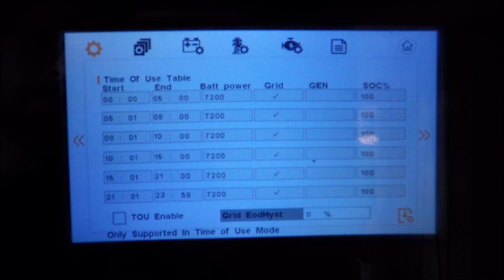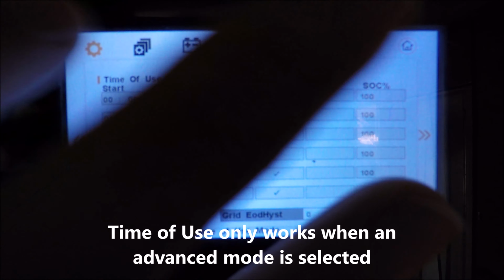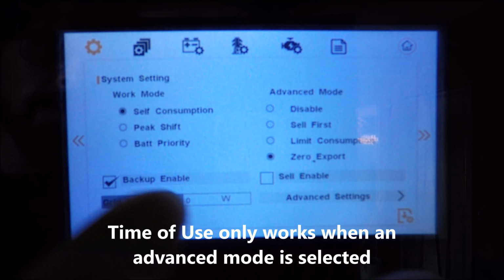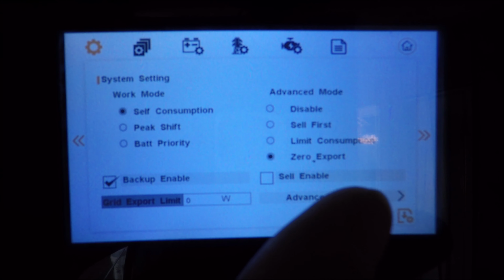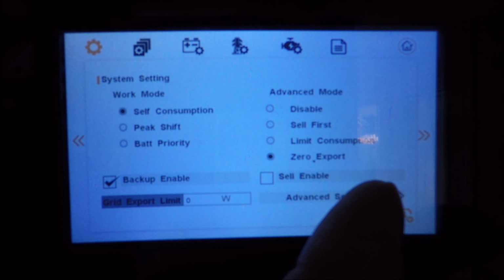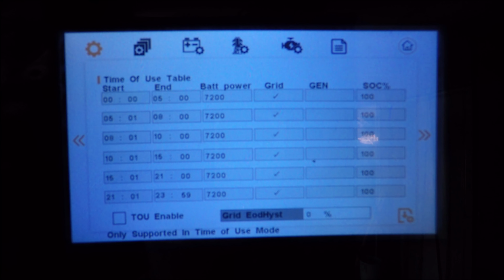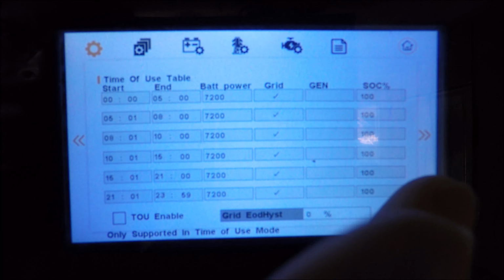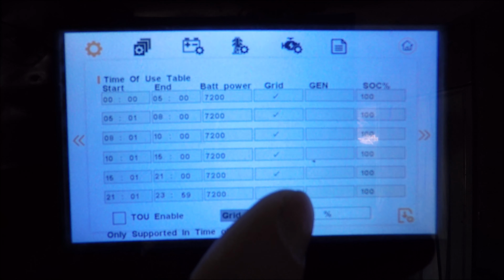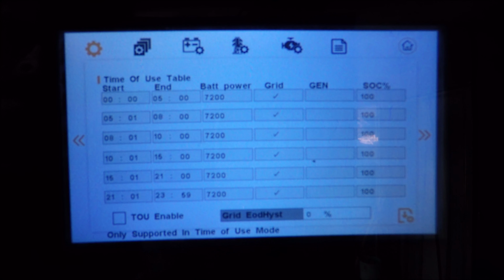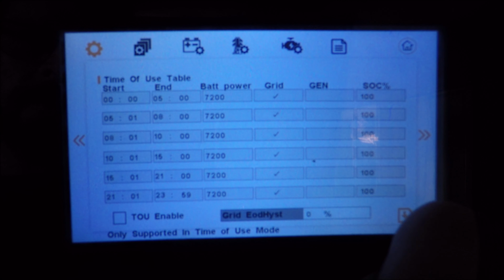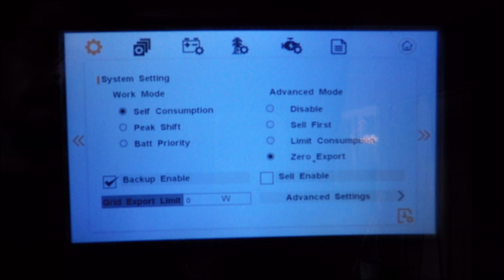To enable time of use, you have to make sure that you are utilizing one of the advanced modes. Time of use, even if you enable it in the submenu, will not work under system settings in the basic work modes. If you have battery communication, you can just simply set your state of charge. You can indicate whether or not you want grid connectivity during those times to charge the battery, and enable your time of use table. After we complete battery setup, we'll revisit time of use to go over some additional settings. So we're going to save these time of use settings for now and go back to the main menu.